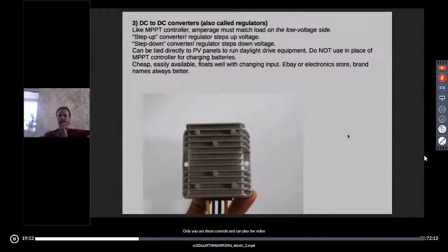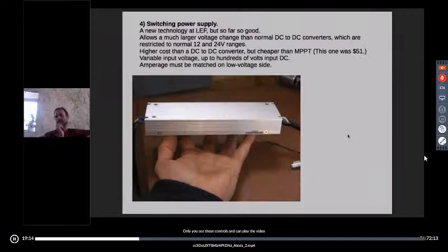A more recent discovery are switching power supplies. Now with those voltage regulators I just showed you, they tend to be set up in standard voltages, which are 12, 24, you might find one at 48. The industrial DC voltages, we'll hit this in a minute, 12, 24, 48, 90, 180. You can have some voltage change, but you want to be near your design voltage.